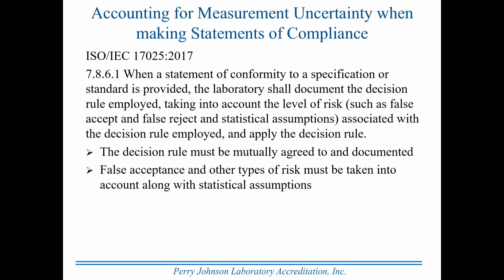If the laboratory was to take it, it's taking a risk that 5% of the measurements for that equipment will be wrong. But it's 95% likely that they're not. And so that's a reasonable ratio. It's a reasonable level of false acceptance risk. And it is what has always, or for the most part, been acceptable to laboratories, and that's the 95% confidence interval being within specification. That's how we used to talk about it. Now in the new version of the standard, they want us to consider that as false acceptance risk, which it is. It's perfectly fine to do so.